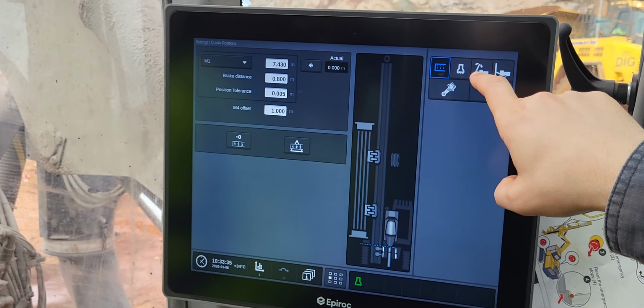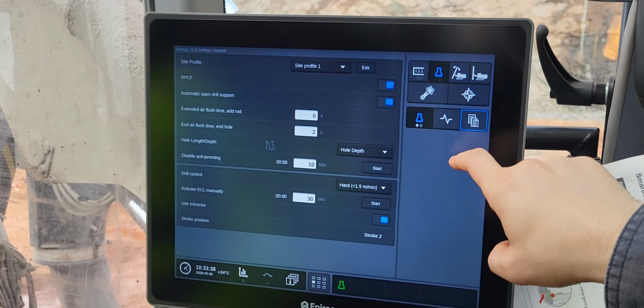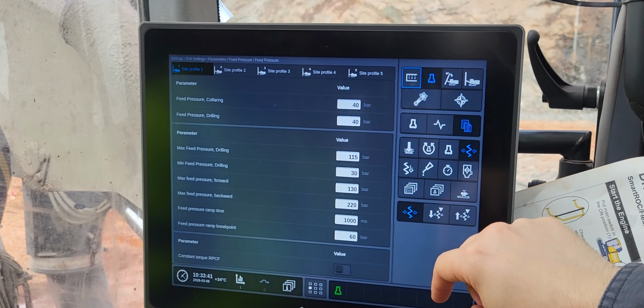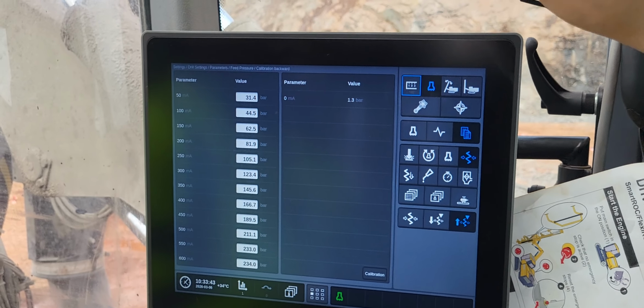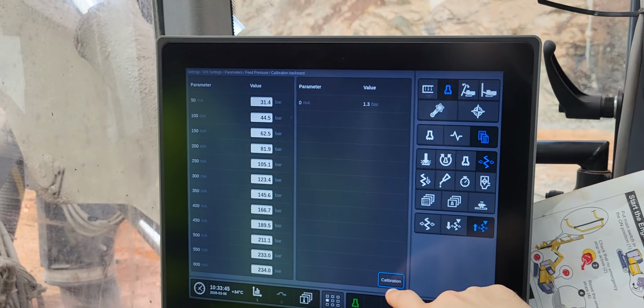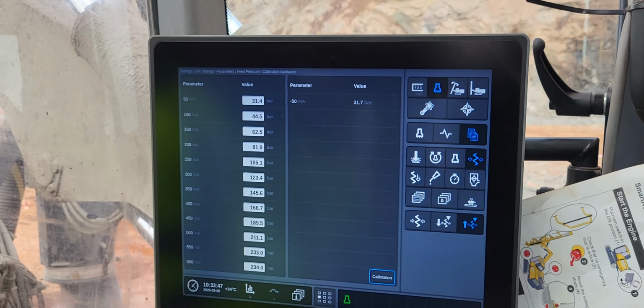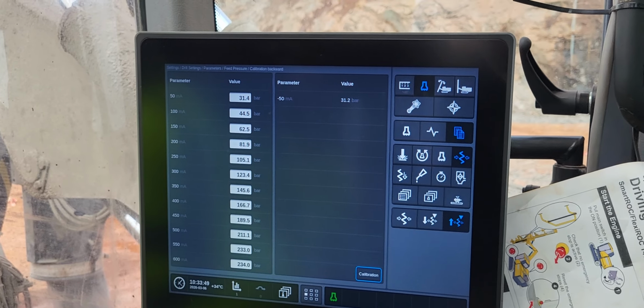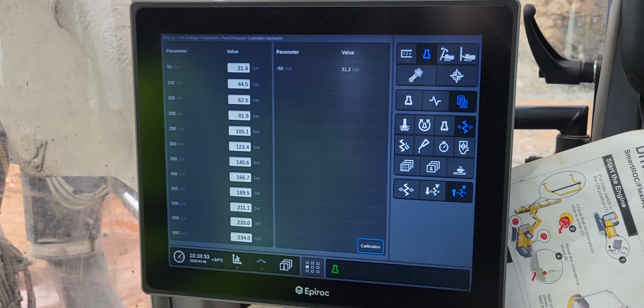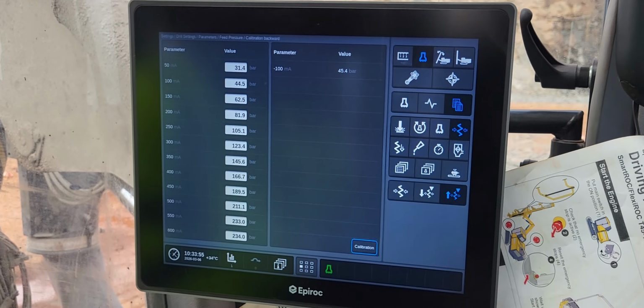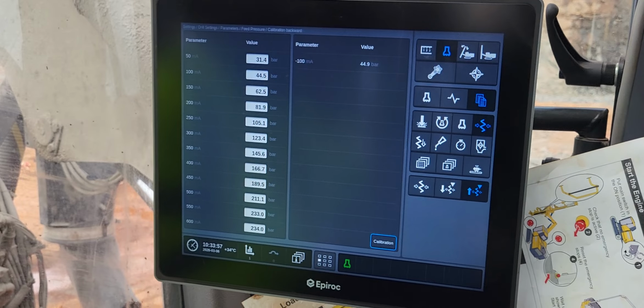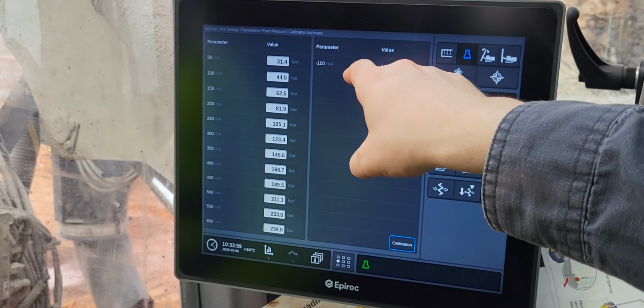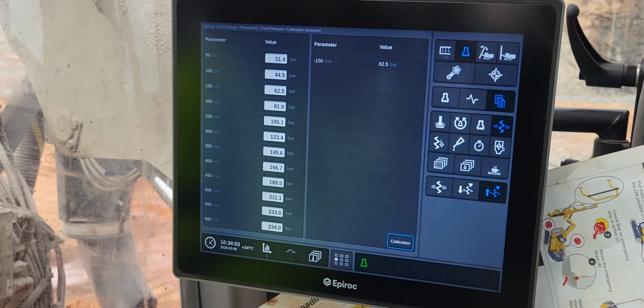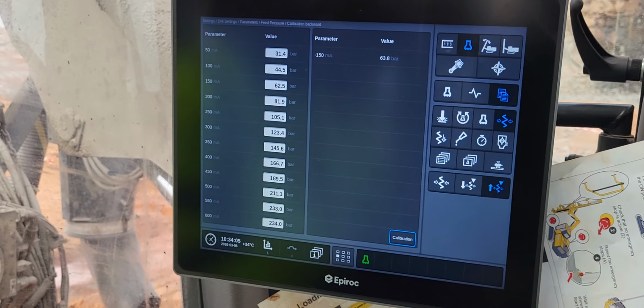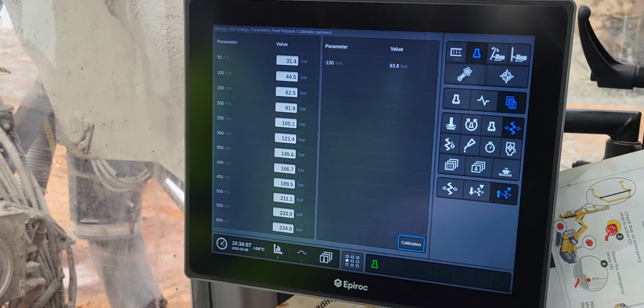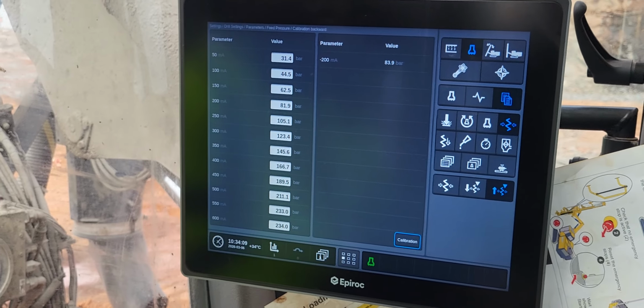And then we do the calibration of the feed. In this case we are on top, so we do the calibration of the feed pressure backward. So you can see when I activate the calibration, the machine is doing it itself, actuating the valve, the feed pressure and feed flow valve, and then making a table with the milliamps and the pressure.